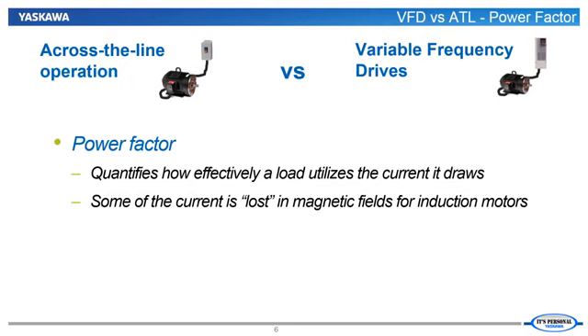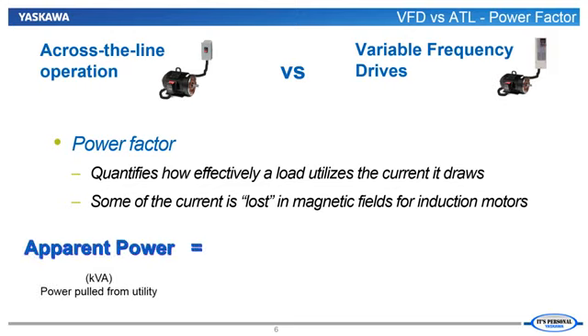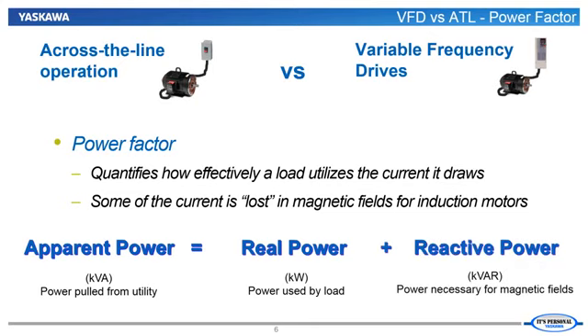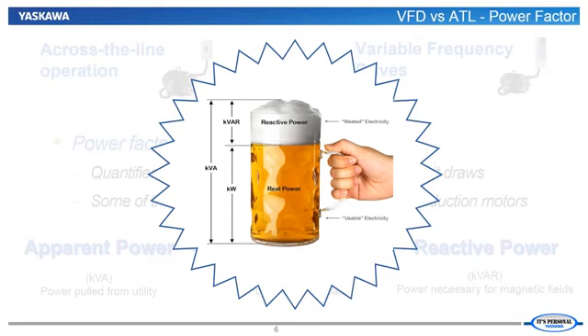One way to think of power factor is that the apparent power pulled from the utility is partly real power, or power used by the load, and partly reactive power necessary to produce magnetic fields. The apparent power is defined as kilovolt amps, or kVA. The real power is defined as kilowatts, or kW, and the reactive power is defined as kilovolt amperes reactive, or kVARs. And now for our familiar visual aid.